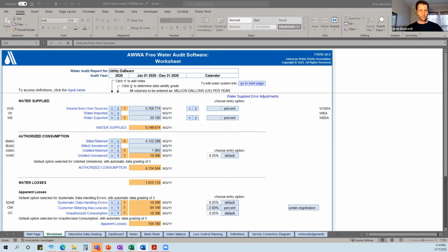Okay. All right. Let's talk about the checking of the meters. Do you know exactly what's involved in that process? I'm not sure. They do something with the meter and the SCADA, but I'm not sure. Okay. So there's actually two tests we need to consider. The first, Steve, is a volumetric accuracy test.